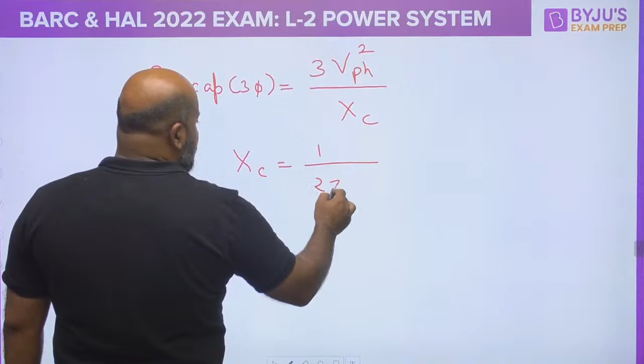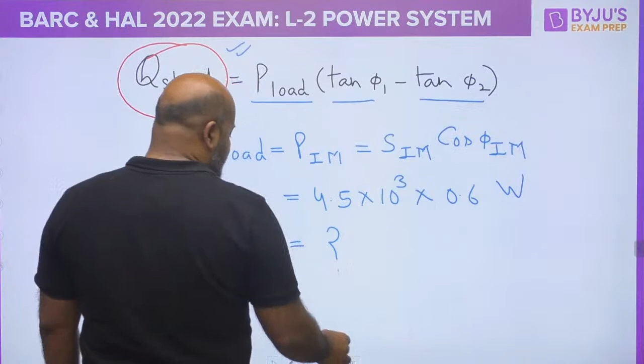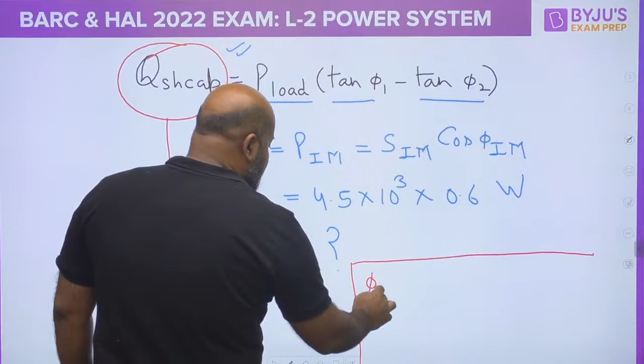Just put this value here. So it is going to be 3 times V phase square, and this is going to be 2 pi f capacitance per phase. Now from this equation, if this value is known, because P load you have just solved, what is this tan phi 1 and tan phi 2? Very easily you can find, because the initial power factor is given.